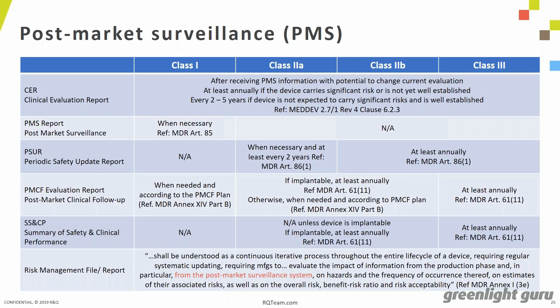So vigilance requirements are very similar between the MDR and the directives with a few exceptions. All serious events must now be reported within 15 days instead of 30 days. So that's quite a bit of a shortening of the time period, but again, it's important to understand that those reports can be followed up with additional information later, so it's better to submit early, get within that 15 days, and then update those vigilance reports as you go. Field safety corrective actions, recalls, corrections, removals, those kind of things require notification, reporting to the competent authority prior to taking action now, so that's a big change.